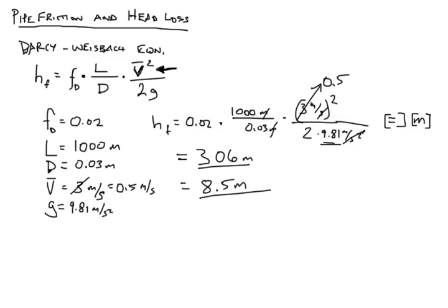And so you can see that by reducing the flow speed to 0.5, we have much less head loss or much less pumping energy required. So you know, the implications of this are really that you can save a lot of energy by pumping slower. At the same time, in a solar thermal energy collection application, that means your fluid would get hotter a lot faster. So this could be a good thing under certain circumstances, and others it could be bad because your fluid could be overheating if it's going too slow through your collector.